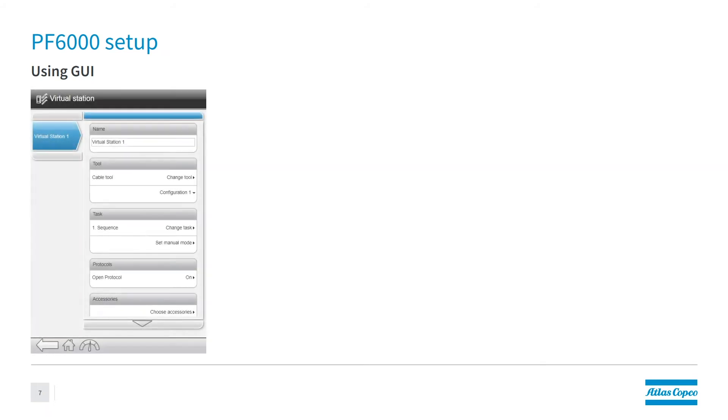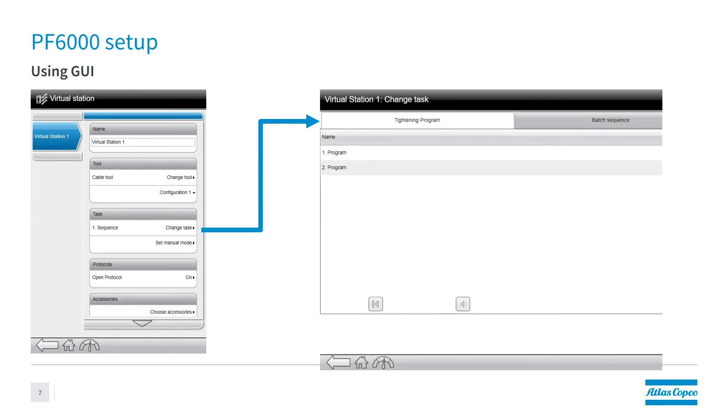Now, in the case of the power focus running internally, we have two different ways of doing this, we can either use the GUI. So the first step you would do is you would go into the virtual station, you would make sure that the open protocol is turned on. Once you've done that, you're going to go into the task, you're going to want to change the task to the tightening program, and you're going to select the program that you want to run.